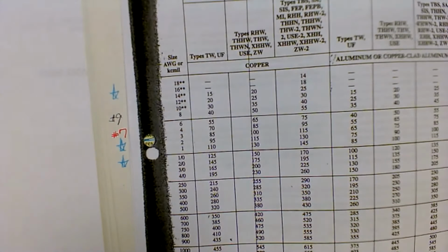Well, let's say when you pull a bundle back in the conduit after it's melted, you need to sit there and look at what we're saying and see if you go right back with what they had. Does it meet code or not? Right. Because you may have to actually run a bigger run of conduit, bigger pipe. Yep. I mean, it may be.